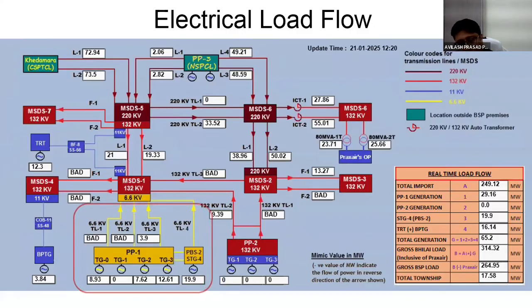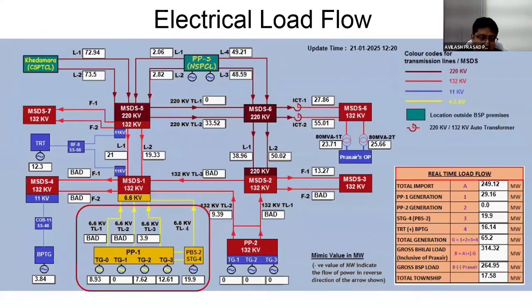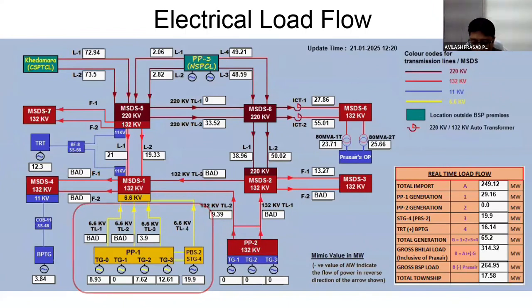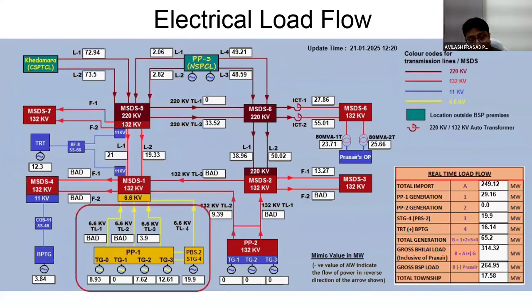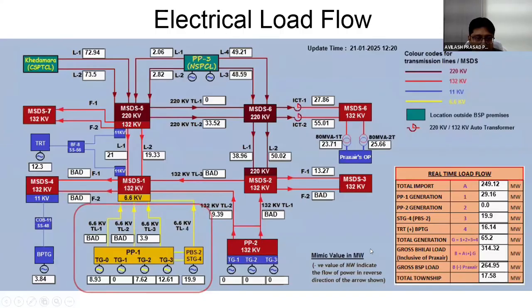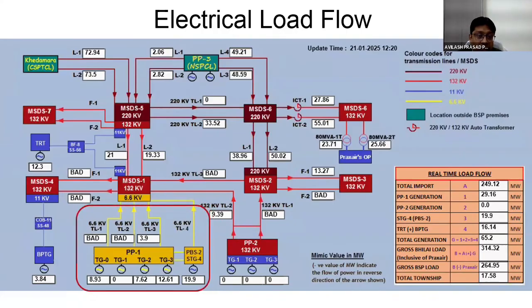Now coming to the main part of our captive power plant, which is called PP1, where we have 5 generators: TG0, 1, 2, 3 and STG4. The capacity of 0, 1, 2 is 12 megawatt each, and for 3 it is 15 megawatt. TG0, 1, 2 are Russian make and TG3 is BHEL make. Here we generate 6.6 kV, and our captive power plant is connected with the grid with the tie line. You can see here it is written as TL1, TL2, TL3. Through this tie line, a step-up transformer, 6.6 kV to 132 kV, is connected, and again it is connected to the grid with the help of MSDS.